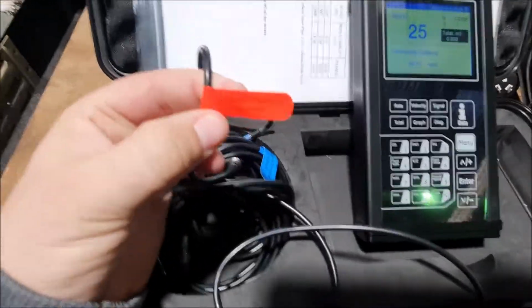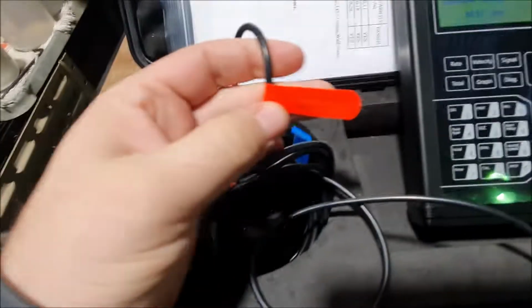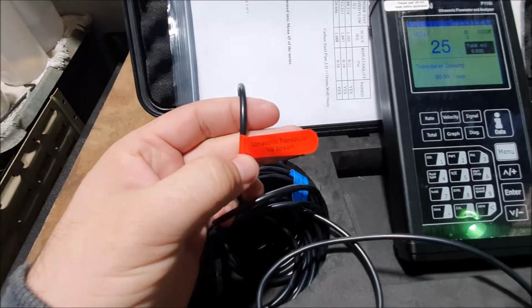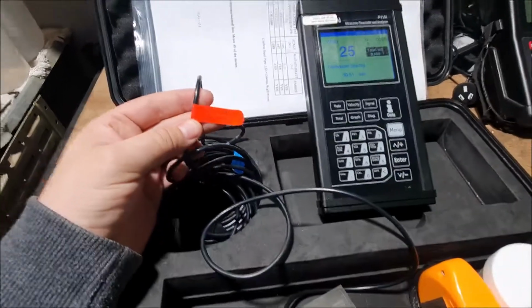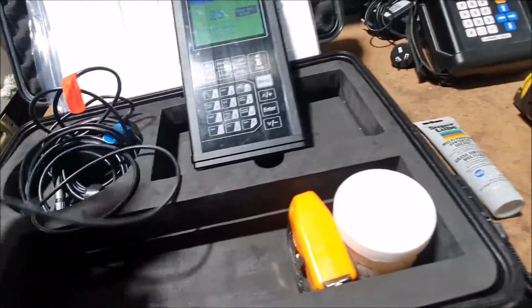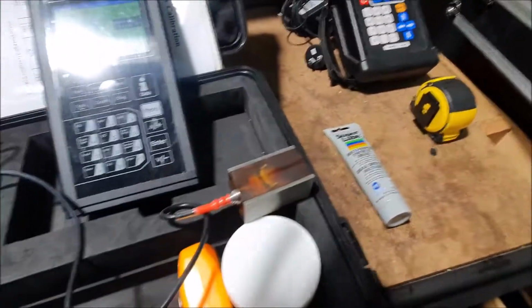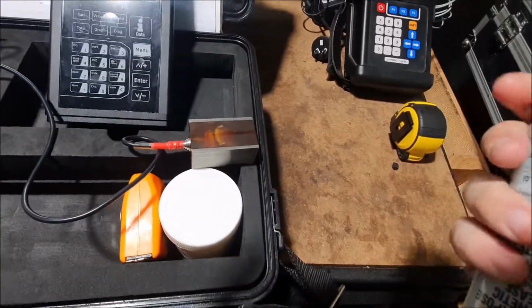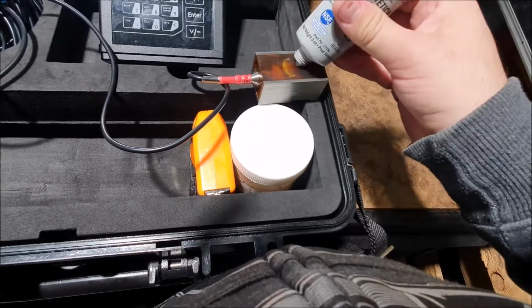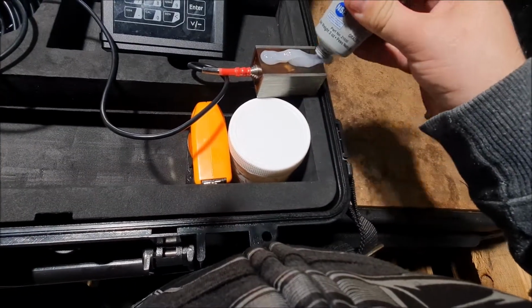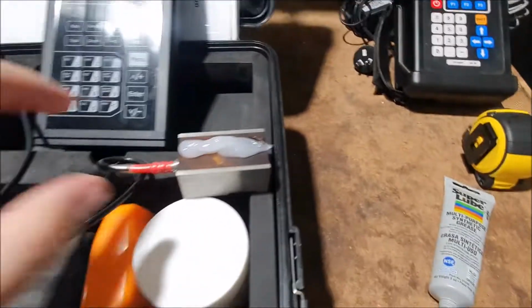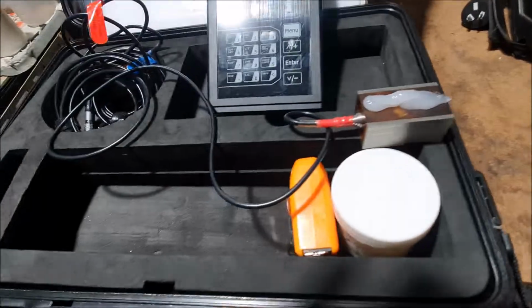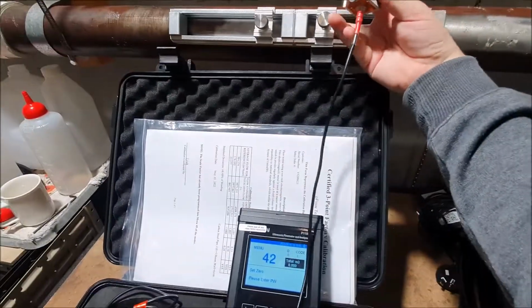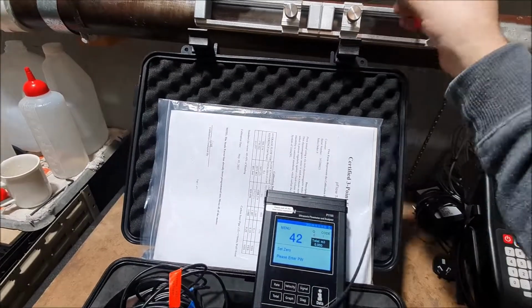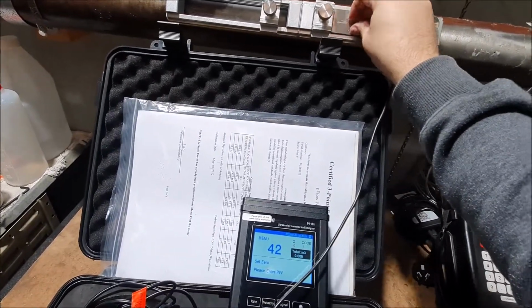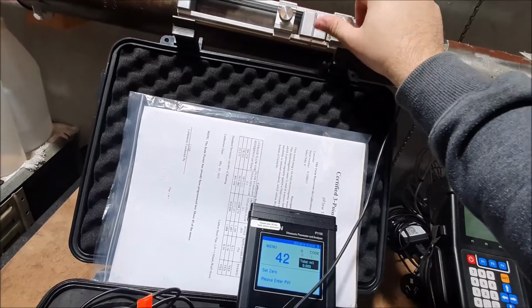Okay, so on these, let's see if I can get it to focus. Sorry, on these little labels, you see this says transducer upstream, so red is going to be upstream. And what we just need to do, take your transducer, grab some couplant, and we just need to basically put a blob of couplant here on the transducer, and then we're just going to slide it into the frame. Let's just make sure this is unscrewed. Slide this into position, and we're just going to tighten this down.